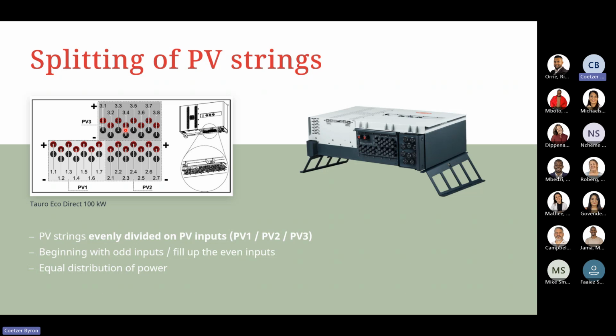What we always recommend is using the Fronius Solar.creator tool to input the data that you are using. It'll ask for the modules that you're using, as well as what version of Tauro or what inverters you're going to be using. And from there, it'll correctly tell you how to string up the unit. It'll tell you, okay, you can get away with splitting 5 strings on PV1, 4 strings on PV2, and 4 strings on PV3, for example. But we always say just double check the data that the Solar.creator tool is outputting against what you have on site.